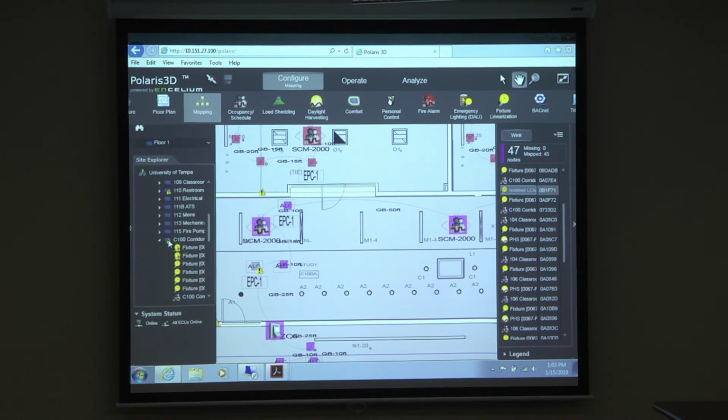In some cases, in the actual design, they intended for that to be an ALC, but in the actual field, they may have omitted the actual ALC, and it's not there. So what should have happened is that the person should have cleaned up the drawings by deleting the stuff that's not there. By deleting them, it will look just like these ones without the exclamation. So if you look at these ones, there are two devices here with exclamations. See this and this?